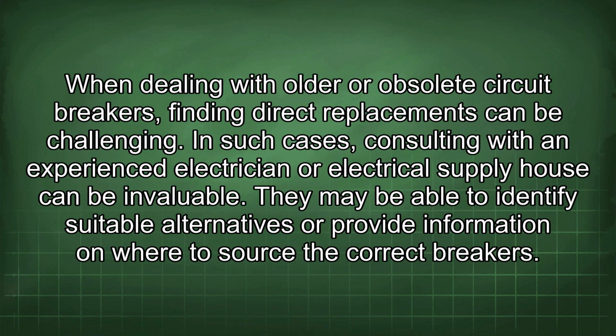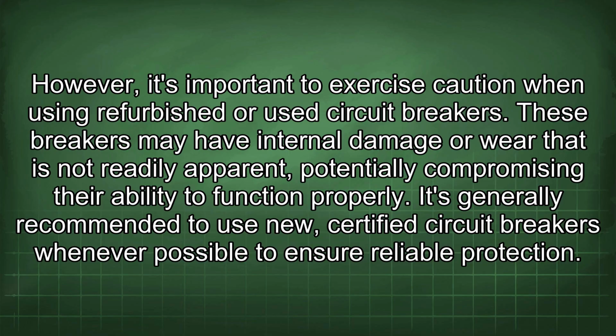When dealing with older or obsolete circuit breakers, finding direct replacements can be challenging. In such cases, consulting with an experienced electrician or electrical supply house can be invaluable. They may be able to identify suitable alternatives or provide information on where to source the correct breakers. However, it's important to exercise caution when using refurbished or used circuit breakers. These breakers may have internal damage or wear that is not readily apparent, potentially compromising their ability to function properly. It's generally recommended to use new certified circuit breakers whenever possible to ensure reliable protection.